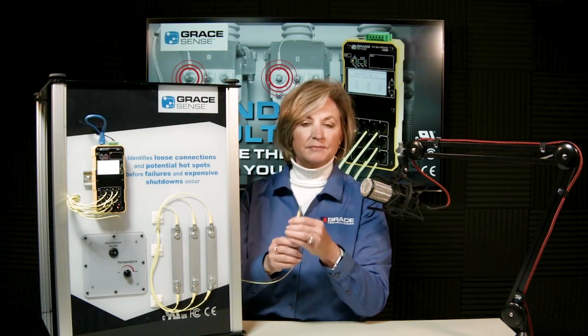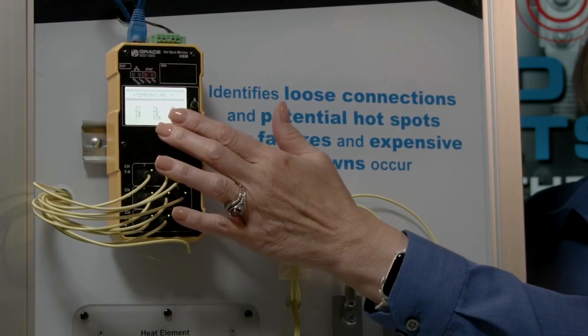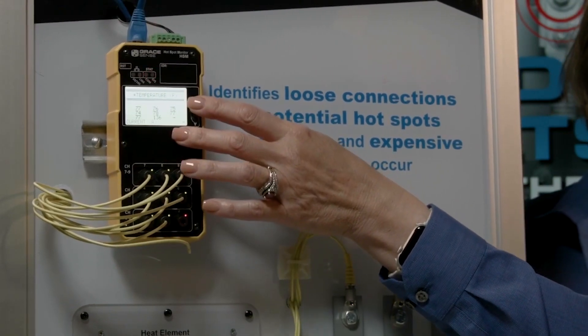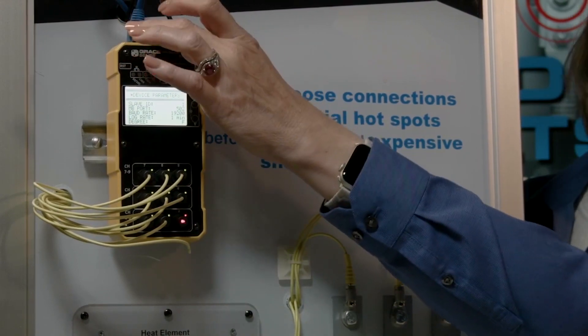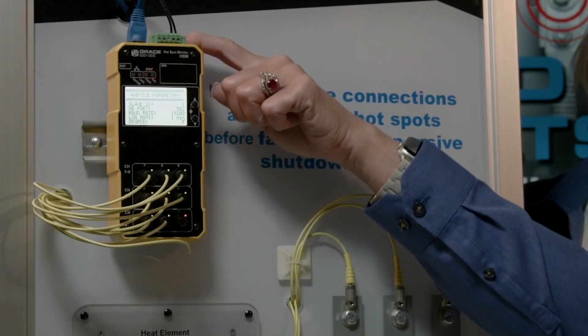The module itself comes in either 9 or 18 points. The 9-point version has an LCD display so you can see the temperature and scroll through all the different values and settings. It has an Ethernet cable supporting Modbus TCP, RTU, or Ethernet IP as protocols to connect to a power management system or existing DCS.